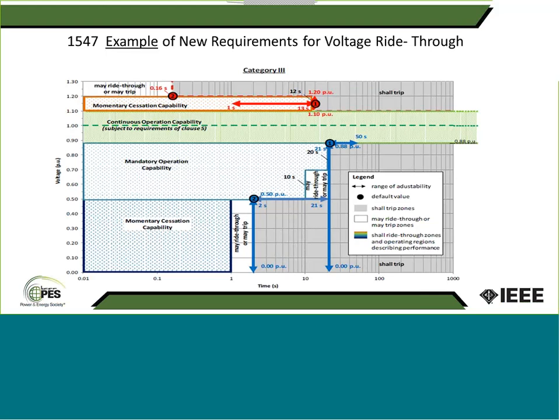But the idea is, again, you see where I'm going with that. The ideal case is let's not even do momentary cessation, and just have the inverters stay on, produce power, and support the grid. On the other hand, there are now issues on the distribution protection side, and we do not have the sort of high-speed protection, like the fiber that we have on the transmission. If we did have high-speed protection on the distribution, you could definitely utilize different types of protection and not let this ride-through concept adversely impact the distribution side. But unfortunately, we don't have that sort of high-speed protection, and that's a challenge for us.